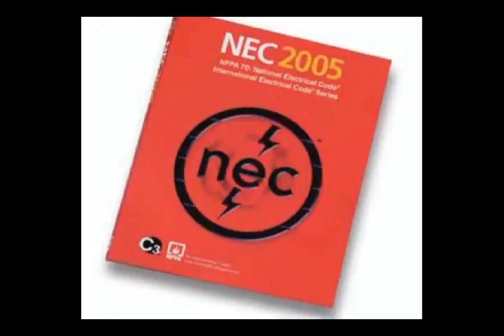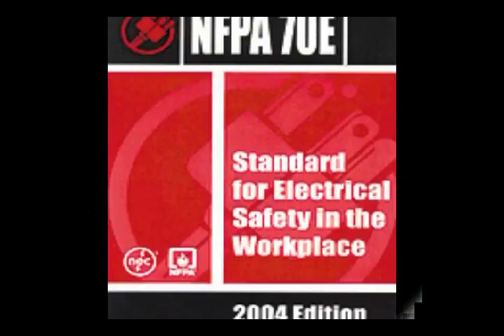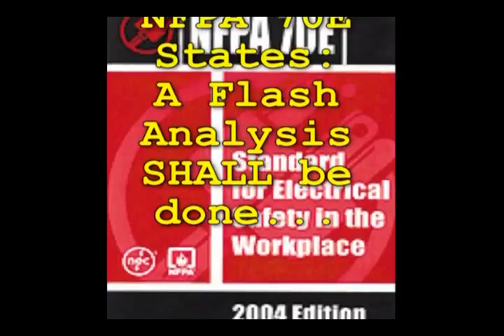Every state in the U.S. uses the National Fire Protection Association's publication known as the NEC, or the National Electrical Code. This code is technically known as NFPA 70. At the request of OSHA, the NFPA published a new standard for electrical safety in the workplace known as NFPA 70E. The NFPA 70E section 130.3 says this: a flash analysis shall be done in order to protect personnel from the possibility of being injured by an arc flash. The analysis shall determine the flash protection boundary and the personal protective equipment that people within the flash protection boundary shall use.